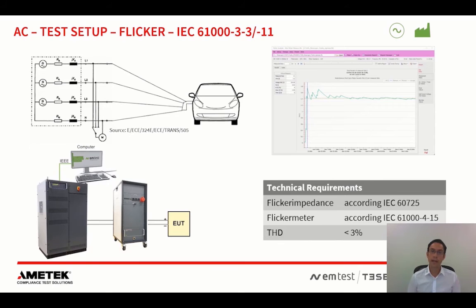And now while the car is charging, it might switch on and off, or might switch in between different voltage levels. And these different currents that flow generate voltage fluctuations or voltage drops over that impedance. These voltage variations are measured by the flicker meter, and there's an interpretation which in the end gives so-called short-term flicker and long-term flicker measurements.